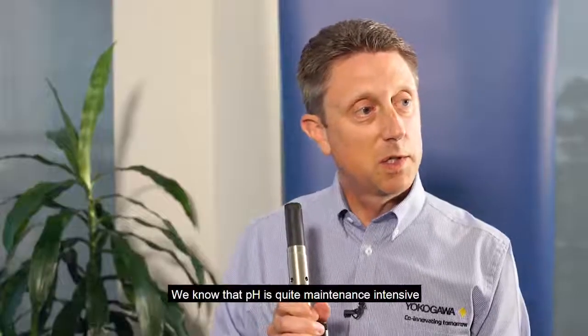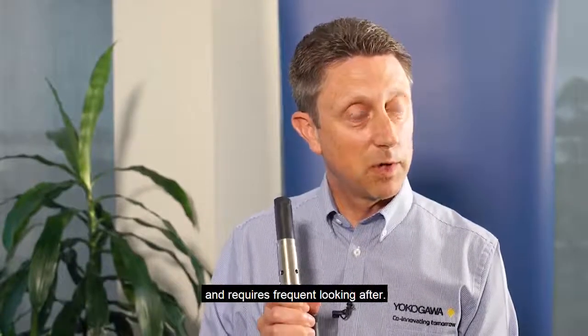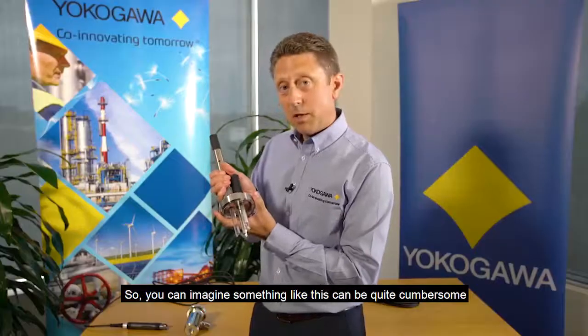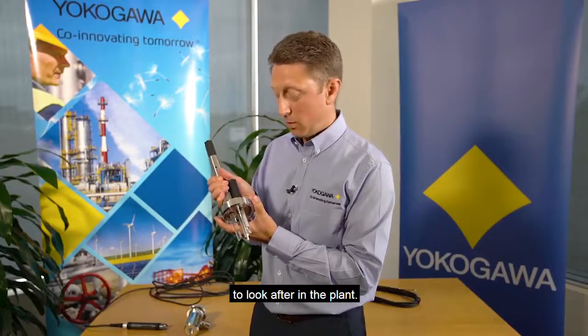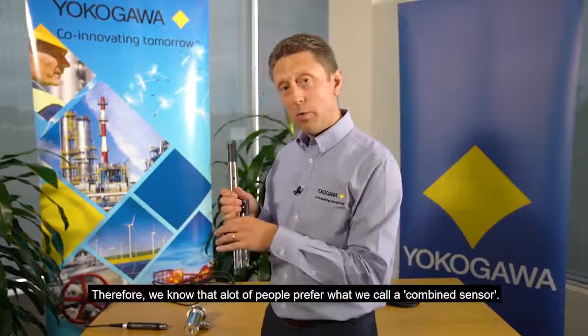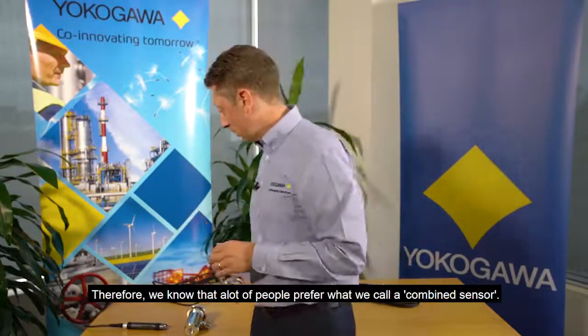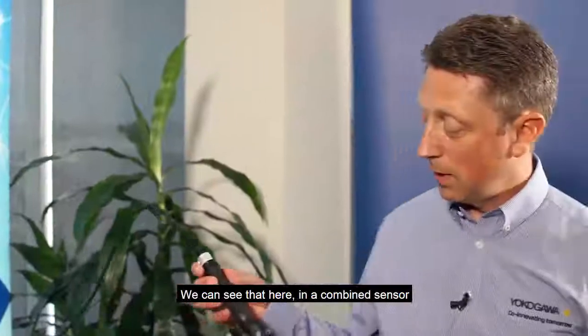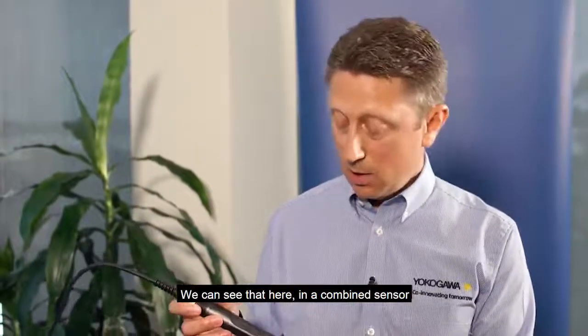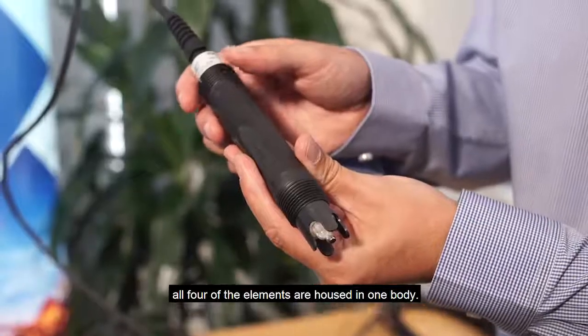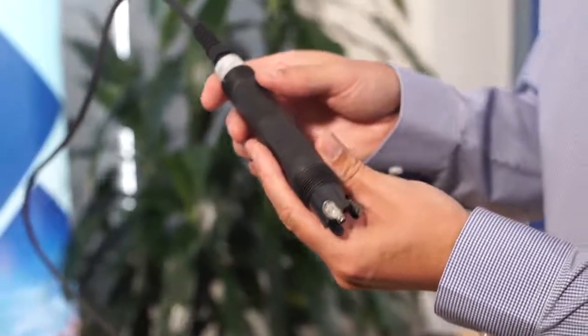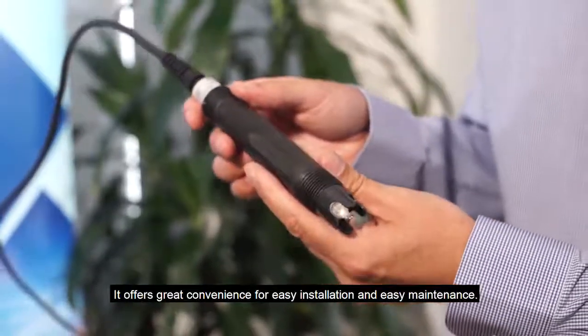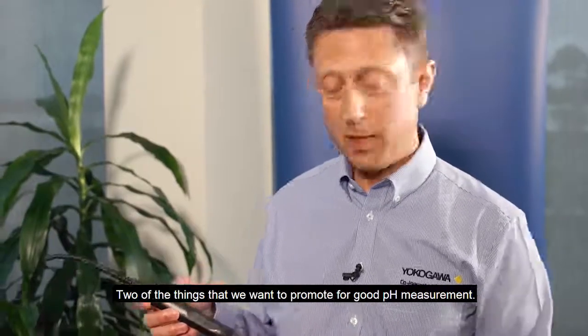pH measurement is quite maintenance intensive and requires frequent looking after, so something like this can be cumbersome to look after in the plant. That's why a lot of people prefer what we call a combined sensor. In a combined sensor, all 4 elements are housed in one body, offering great convenience for easy installation and easy maintenance - two things we want to promote for good pH measurement. However, it doesn't offer great flexibility in your choice.